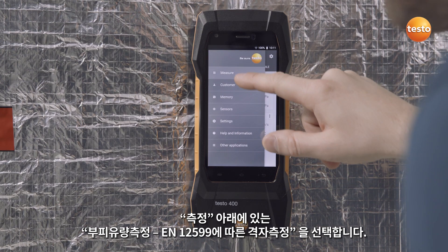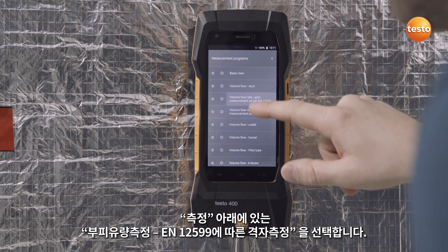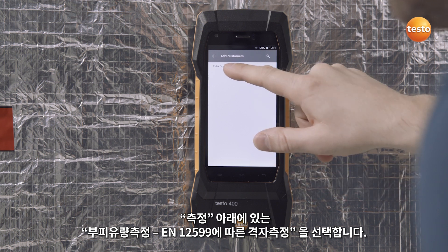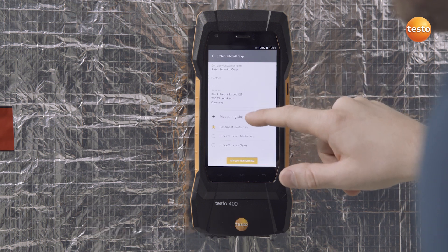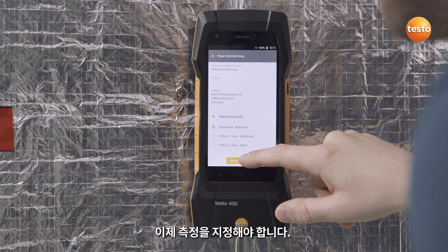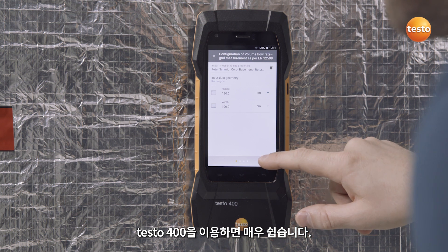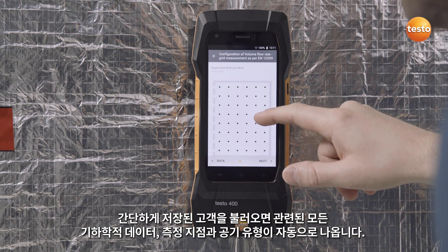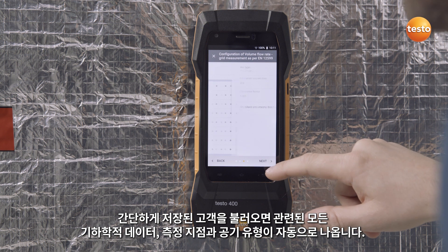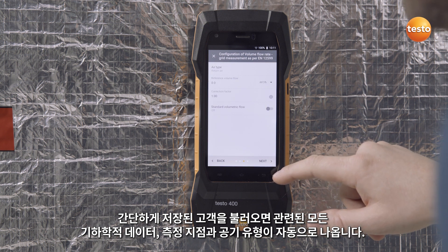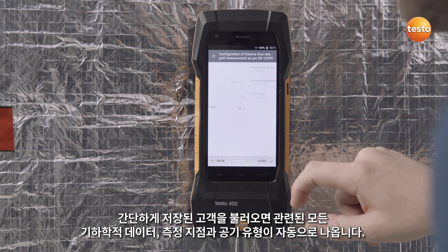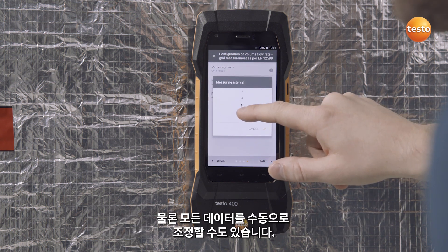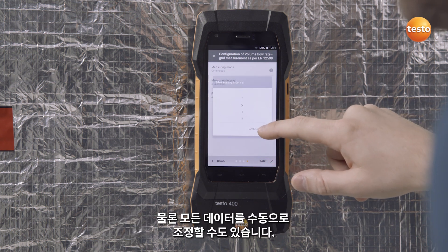To do this, select Volume Flow Rate Grid Measurement under Measure. Now the measurement has to be configured. With the Testo 400, this is especially easy. Simply import a stored customer and all corresponding geometric data, measurement points, and the air type are automatically taken over. All data can, of course, also be manually adapted.